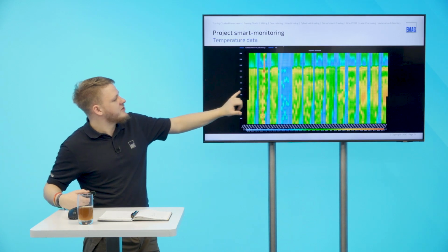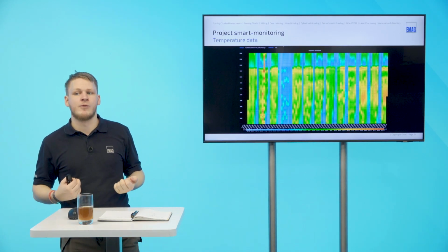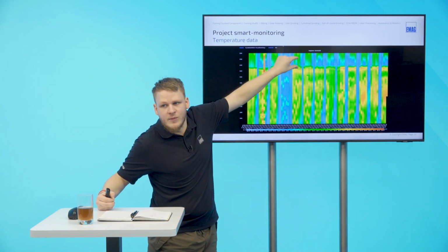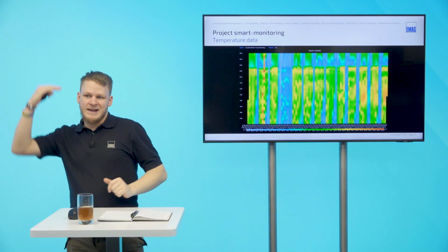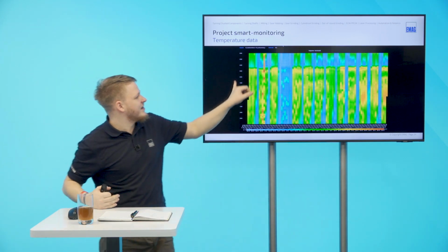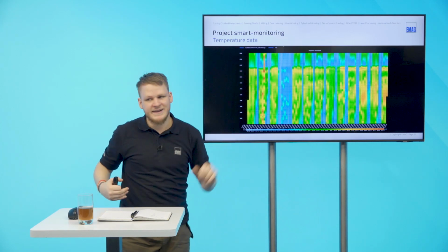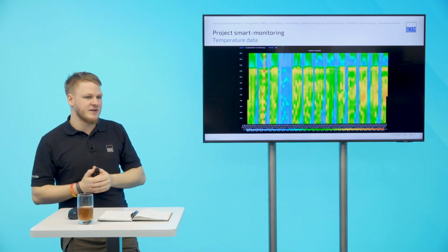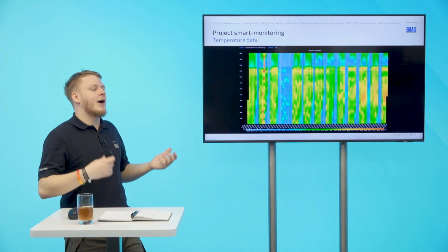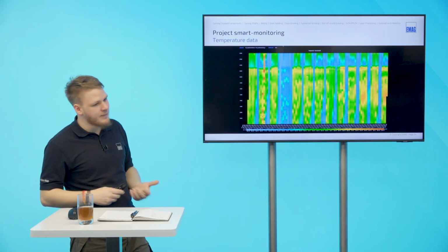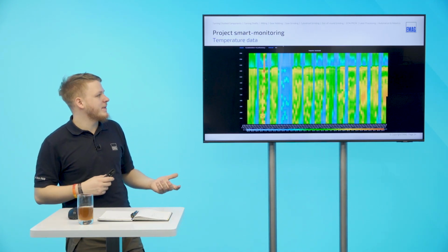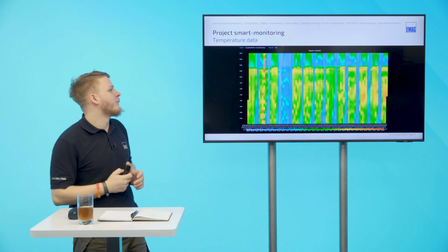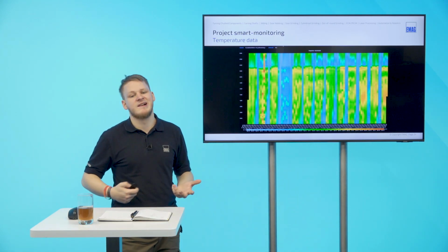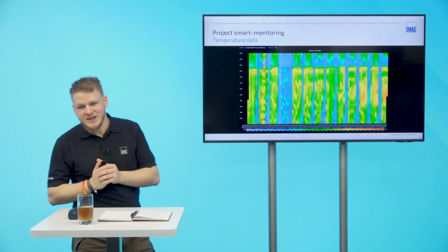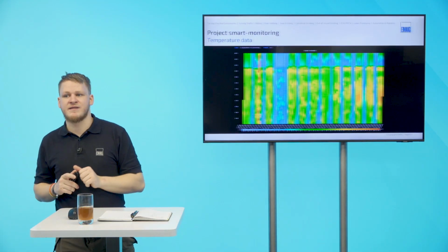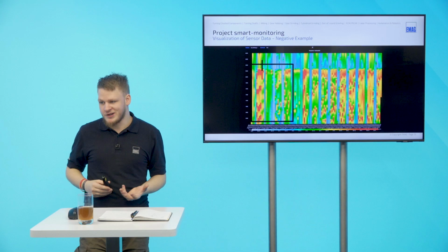And we were able to observe this with this heat map chart that it's actually working, because you see how in the morning hours before 6 a.m. it slowly drops down the temperature and starts heating just around about 5:30, so the factory is warm when you need it. You can also see how long my factory needs to heat up. Based on outside temperature, you can maybe compare that and even adjust the preheating times, or in general see if you have issues. Speaking of issues, I actually brought a negative example of how it should not look.